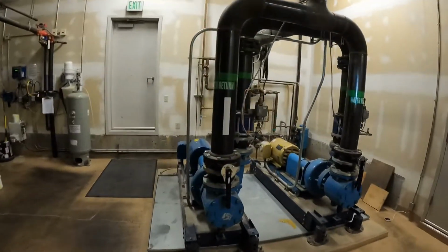So we've taken the heat from the building, transferred it into the refrigerant, brought it into those condenser barrels, and now we've taken the heat back off that refrigerant and we put it in water. So right now, that heat from the building is in a water loop. That water loop's coming over here to go through these pumps headed outside. So we go outside.